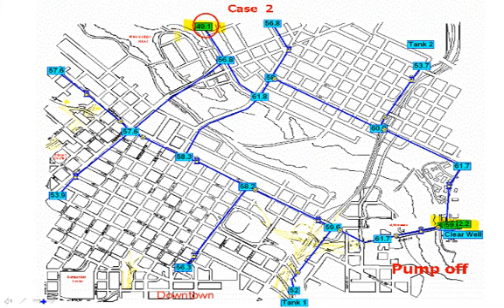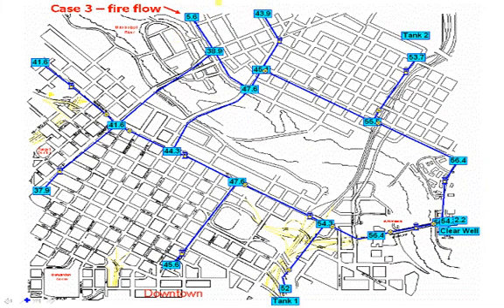Finally, we add a fire demand of around 700 gallons per minute up here, and we see the pressure is down below 20 PSI — too low. This indicates the distribution system can't provide that much fire flow at that point. The real point here is that we can quickly make these evaluations in just a matter of seconds.